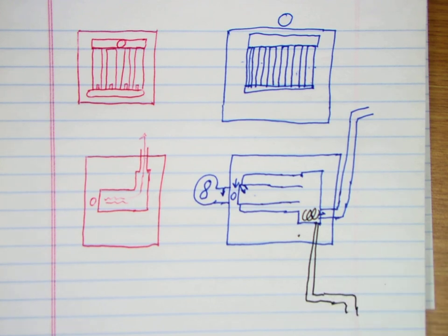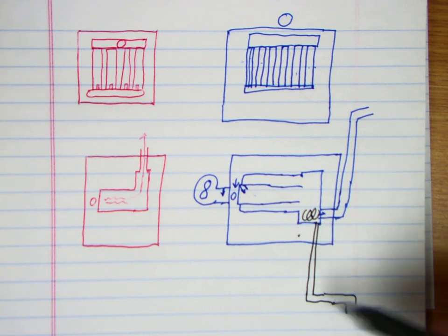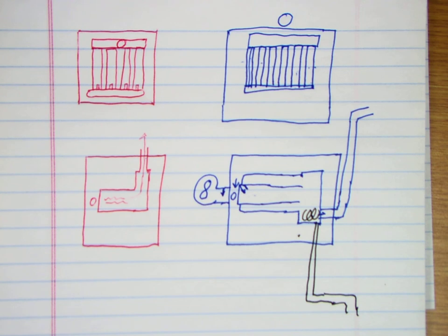Now, when they first started to come out, people didn't know a lot about them. They used to just run this pipe down onto the floor. If it was within a foot or so of the floor drain, they didn't worry about it. Problem is that three or four months later, partway through the first winter after these furnaces got put in, they noticed that all the concrete where that water was draining out was eaten up.